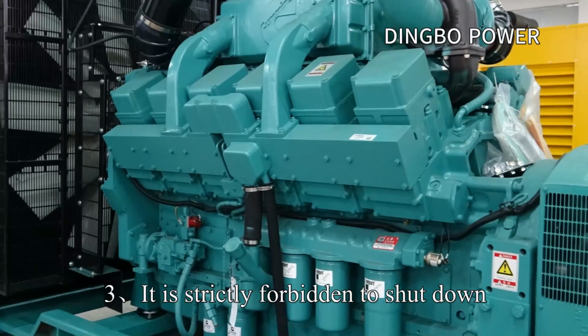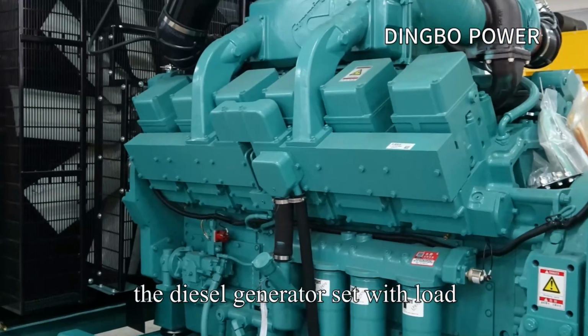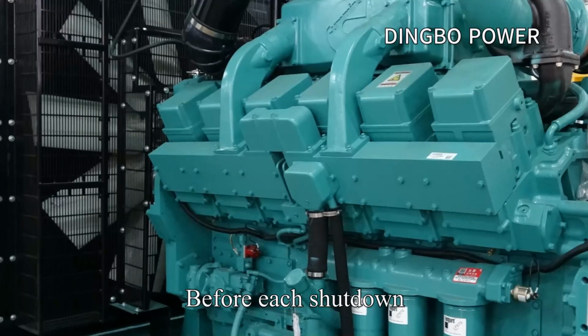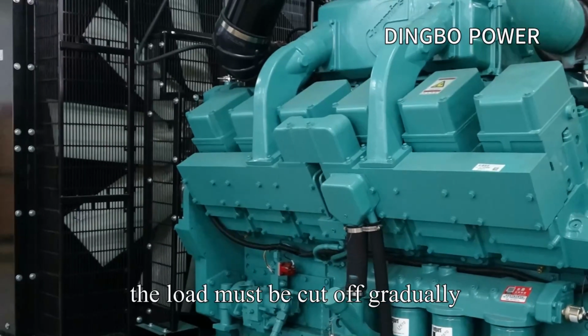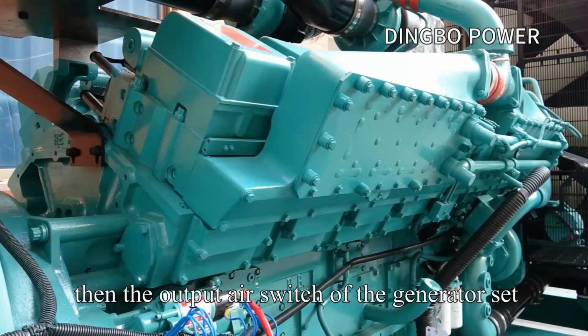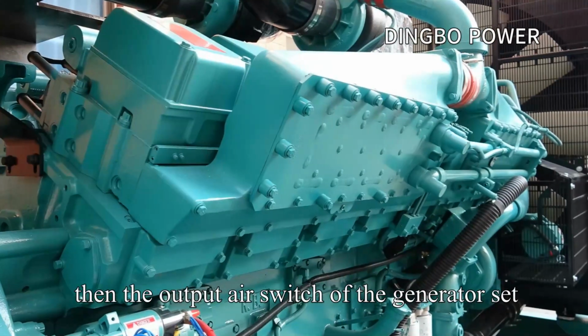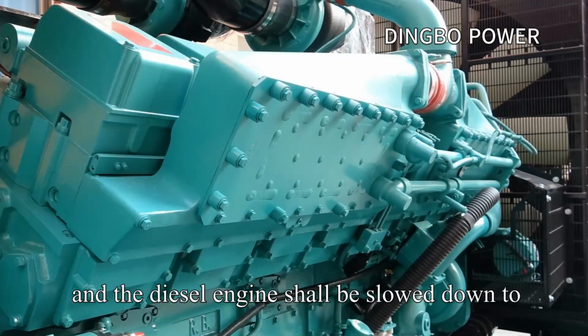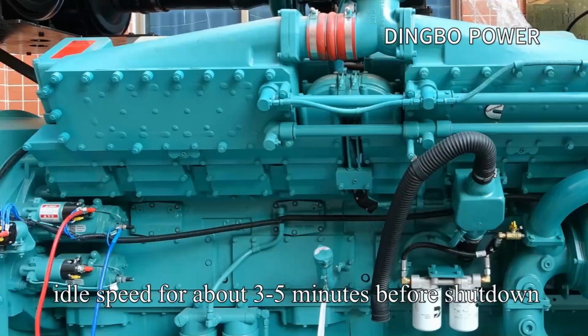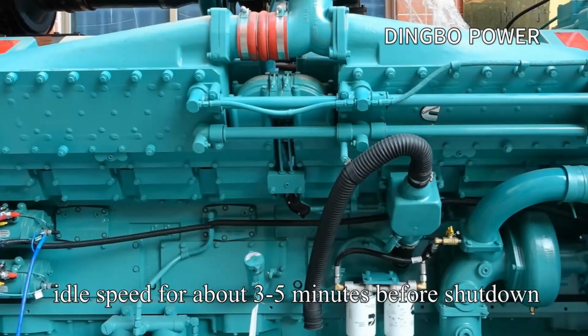Third, it is strictly forbidden to shut down the diesel generator set with load. Before each shutdown, the load must be cut off gradually, then the output air switch of the generator set must be turned off, and the diesel engine shall be slowed down to idle speed for about 3-5 minutes before shutdown.